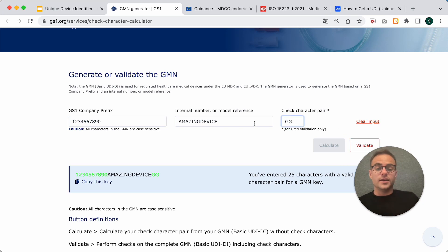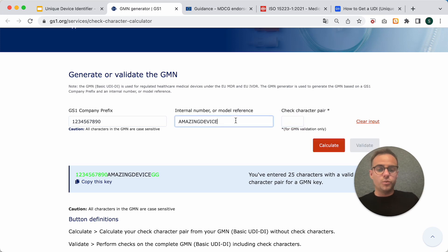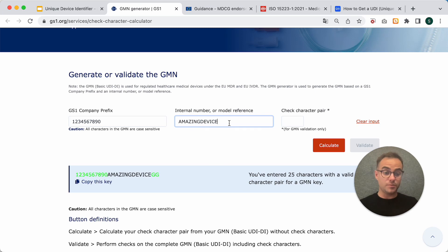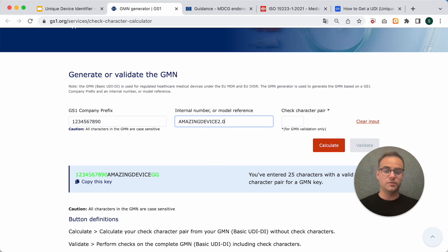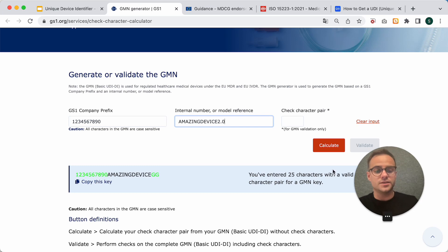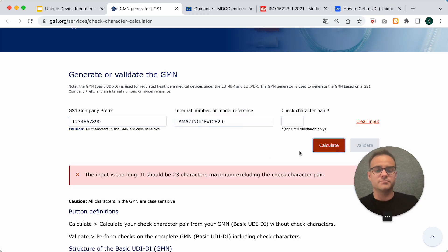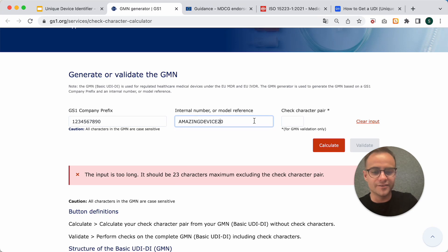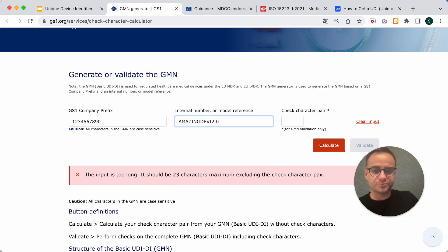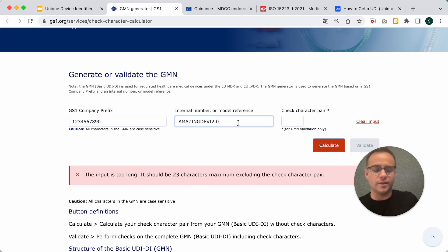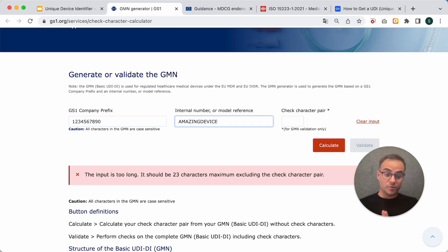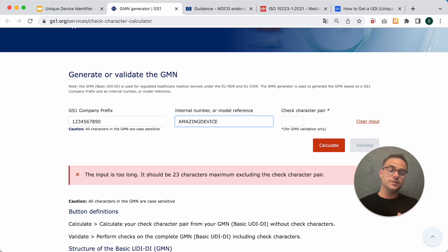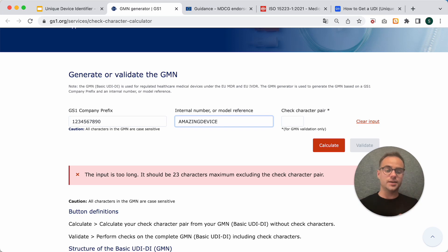All right. I would recommend to just put the device's name here. Sometimes I see it that people enter a version number here. This is not so ideal. And also, you cannot do it, actually, because it's too long right now. I wouldn't enter a version number here because this basic UDI-DI describes your whole product. And that's independent of the version.